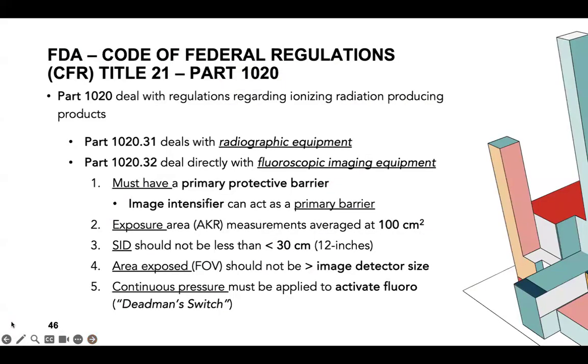So fluoroscopy regulations. The FDA does come into this, as well as with mammography. The FDA's Code of Federal Regulations, CFR Title 21, Part 1020, deals with regulations regarding ionizing radiation producing products such as our fluoro machines. Part 1020.31 deals with radiographic equipment. 1020.32 deals directly with fluoro imaging equipment. It tells us that our imaging equipment must have a primary protective barrier. Our image intensifier on our fluoro machine can act as a primary barrier, but we also have that lead curtain there as well. That can be considered a primary barrier.